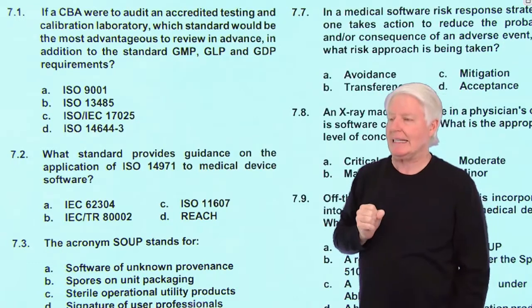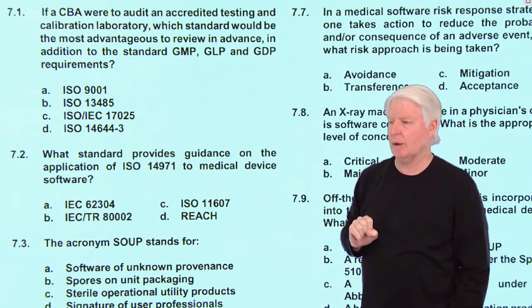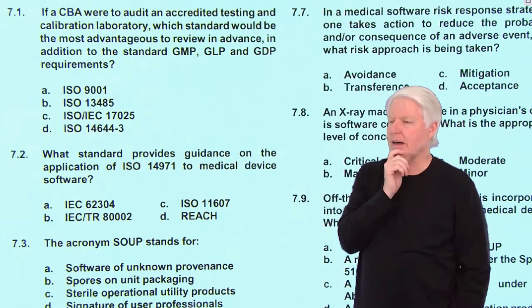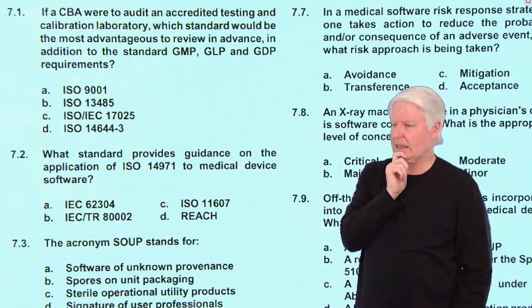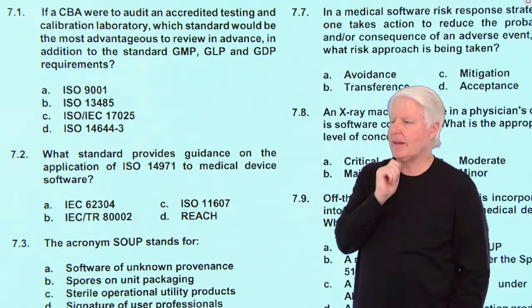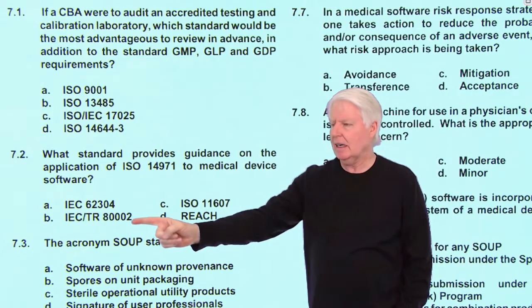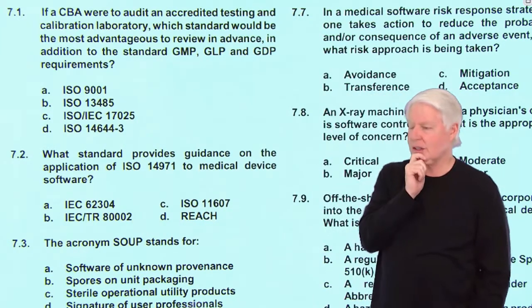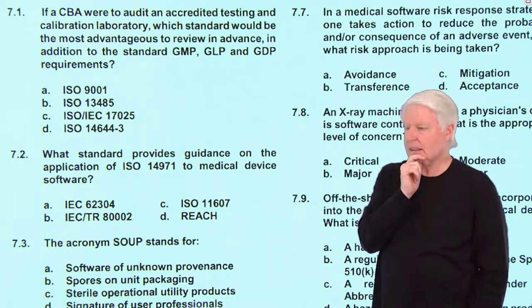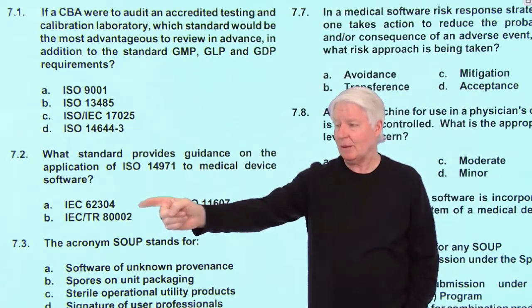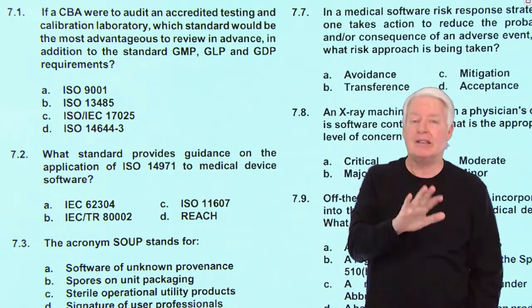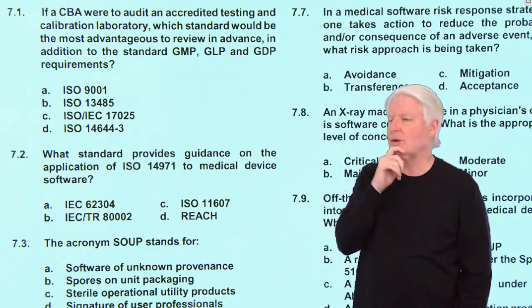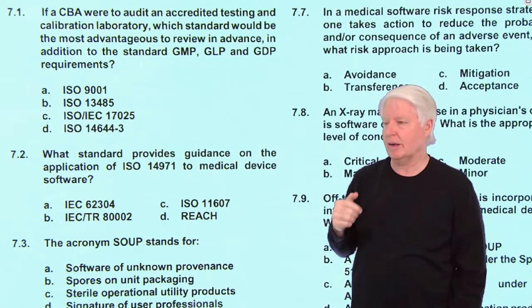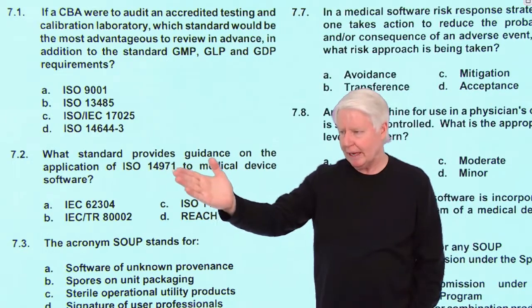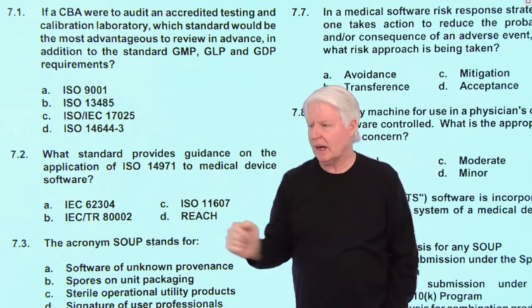7.2: what standard provides guidance on the application of ISO 14971 to medical device software? That is going to be IEC TR 80002. I can see why you'd pick IEC 62304—it is about software, but it's a software life cycle type standard, so that doesn't answer this question. The application of ISO 14971 is IEC TR 80002.